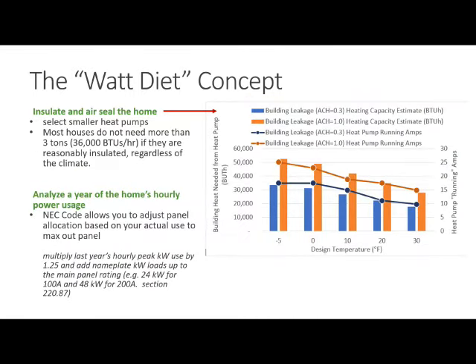Talking about the envelope, it's important to insulate and air seal the home, especially in colder climates, so you end up using a smaller heat pump to heat and cool your house. Most homes do not need more than 3 tons if they're reasonably insulated, regardless of climate. In the Ohio case studies I showed earlier, they tried to get the heat pump size to around 3 tons, improving the shell to meet that size, which is an interesting strategy since most ductwork is designed for 3-ton systems.